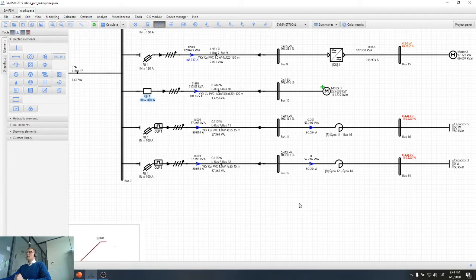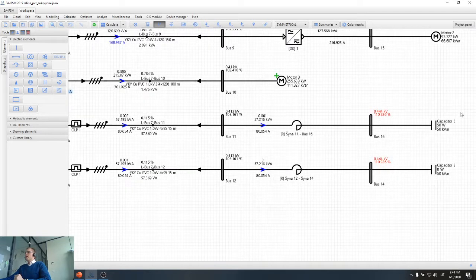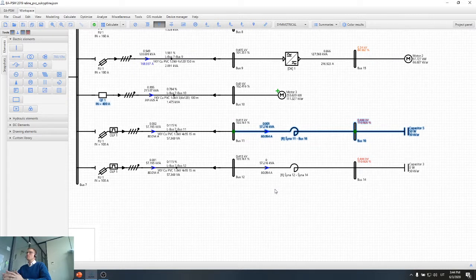Let's go further on and now talk about the capacitors protection. Here we have capacitors with harmonic filters. However, the biggest problem which affects capacitors is actually harmonic currents that overload the capacitor and increase its temperature. In order to avoid harmonic overloading for the capacitors, it is recommended to use reactive power automation devices that have built-in harmonics measurement, and according to predefined limits for the current and voltage harmonics, they disconnect the power bank if these limits are exceeded. So the best protection for the capacitors from overloading is basically a reactive power bank automation device.